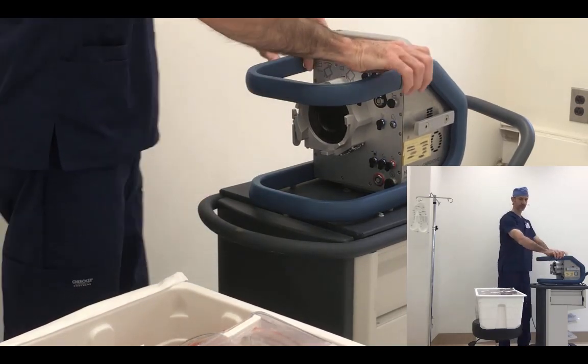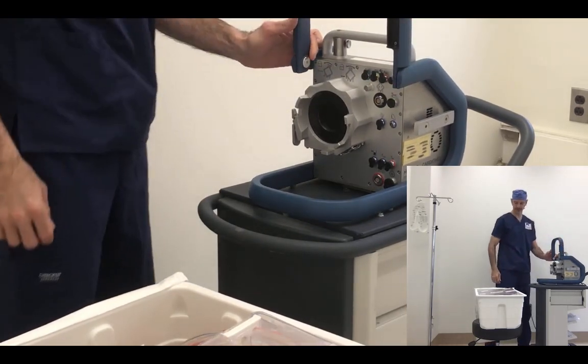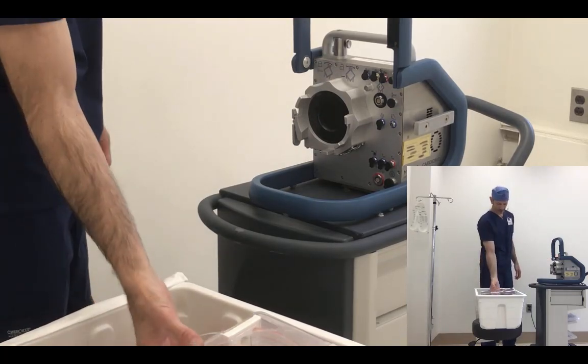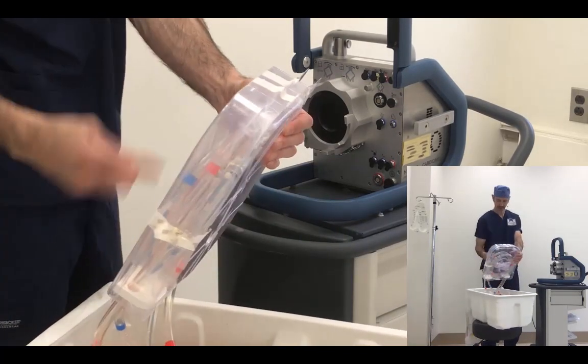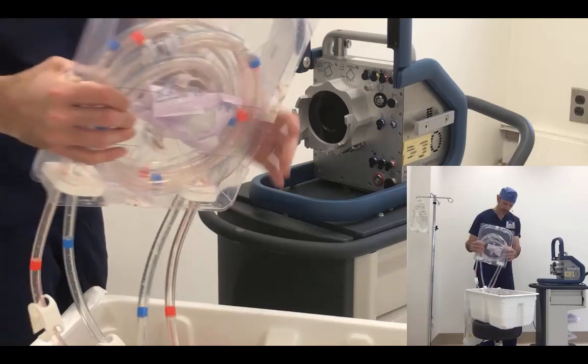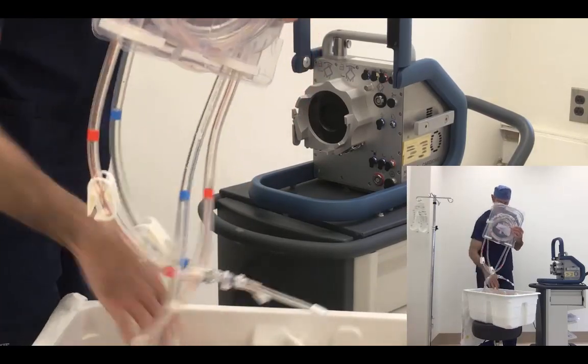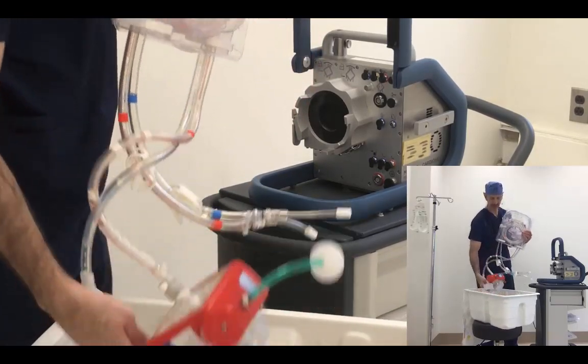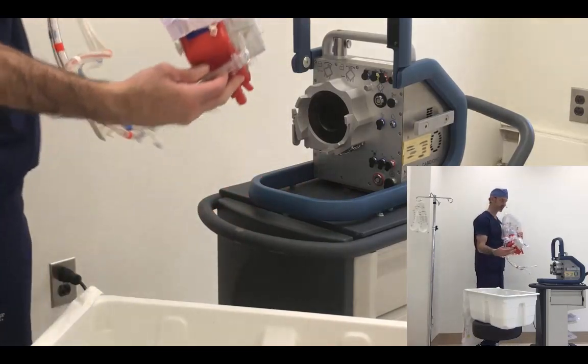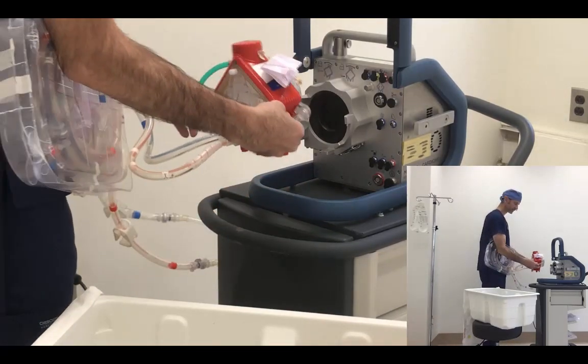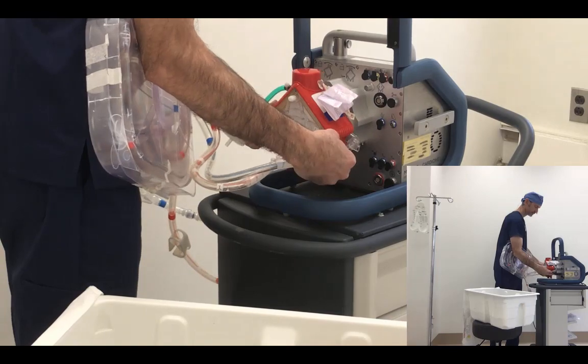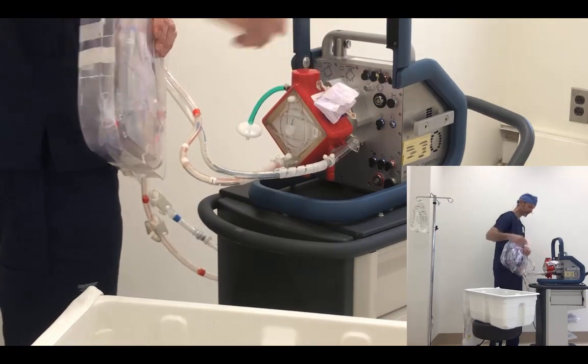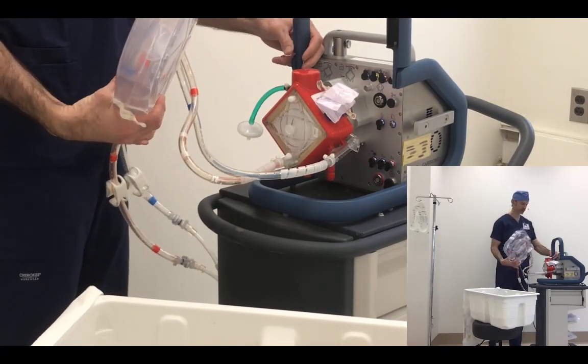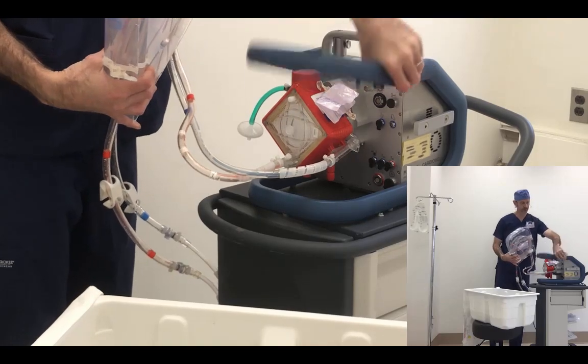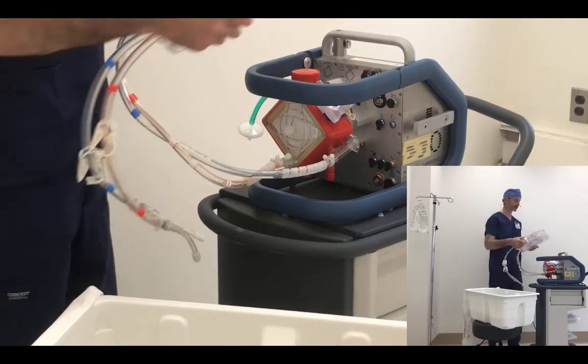Open the door with 2 buttons. Flip that up. And take the tubing loop and the pump oxygenator cassette, the HLS set, out of the tubing pack. And put this in, locked in place. I can drop the door and could place this on top.